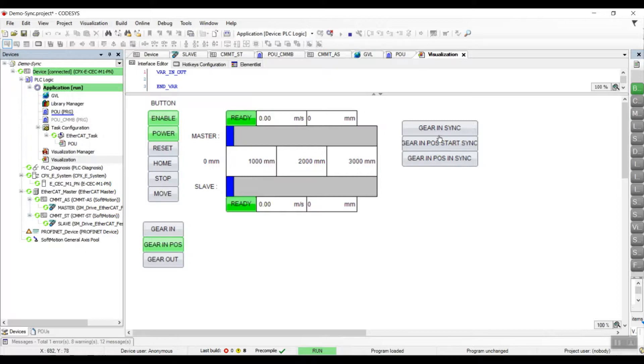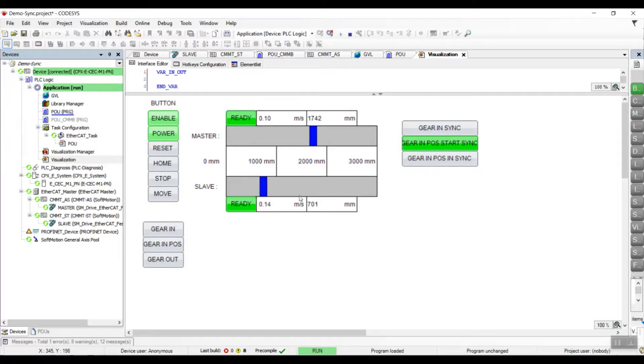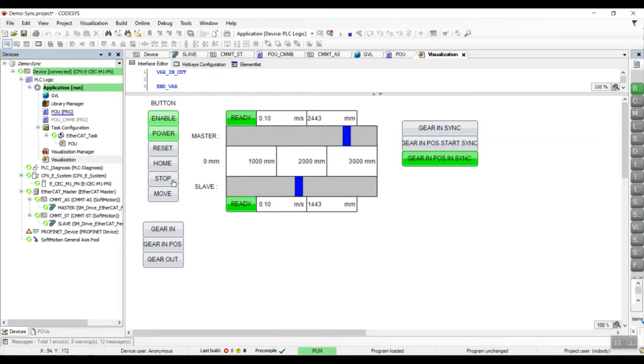We can see that both drives are not in sync yet. We'll trigger the move velocity bit and move the master. Once the master position has reached 1 meter, we can see that the status is now 'start sync'. At this moment the slave will start moving, but the velocity is not yet in sync with the master. Once both drives have reached the setpoint position, we can see that the positions and velocity are now in sync, and at the same time the status has also changed to 'in sync'.